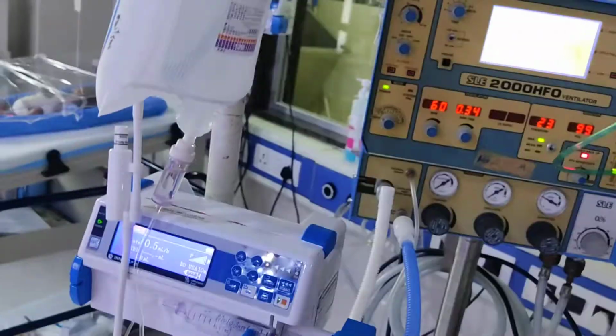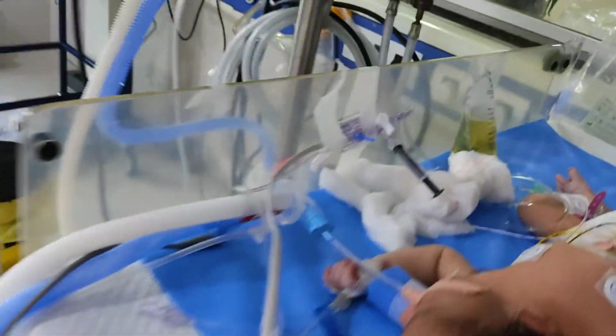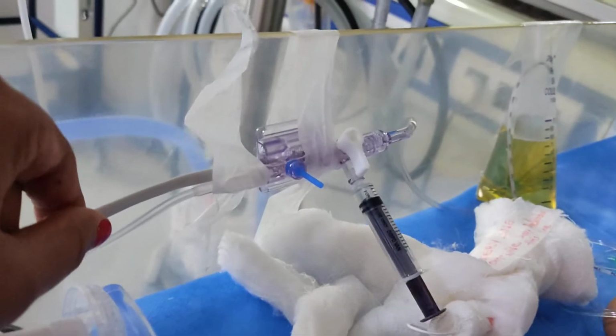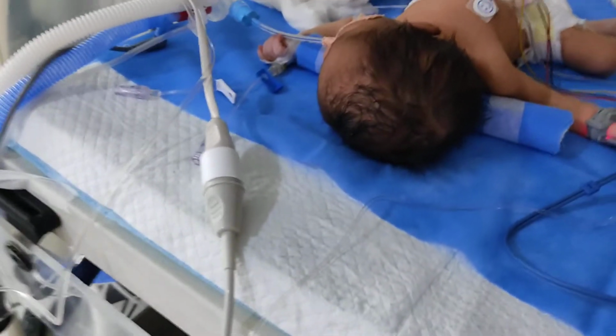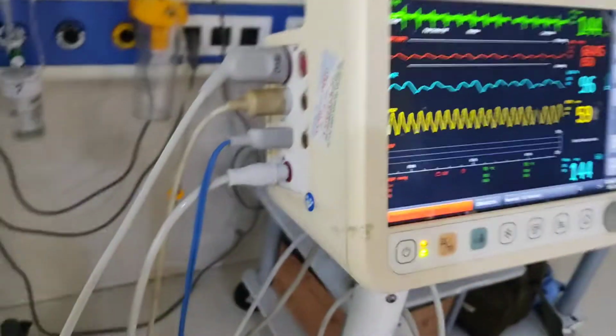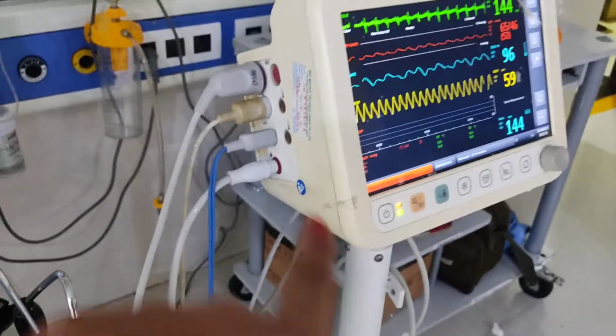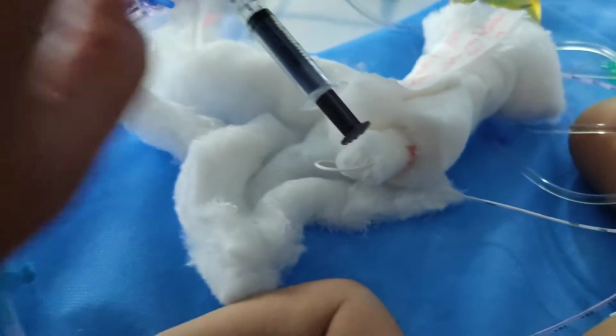So you have to see, first is the pressure bag, then we have to inflate the pressure till 250 to 300 mmHg. Then we have connected this one end to this device, second goes to the arterial line, and third is to the syringe. And we have connected this to the transducer. Okay, and this transducer goes to this multipara monitor. Now one technique is very important here. Every 2 hourly we need to flush. So I will show you the technique how to flush this line.